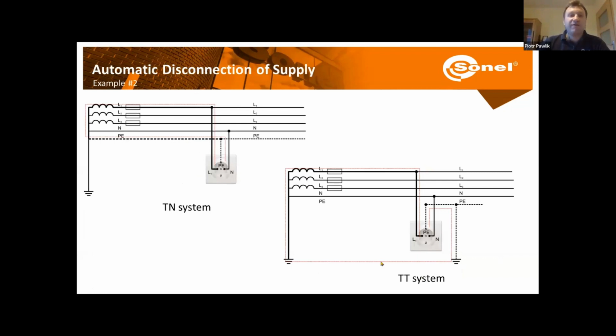Okay, so here lower value will be in case of a TN system. Let's look over here. This is our fault loop, the red dashed line. In case of a TN system, it is closing through a protective wire, so just a piece of metal in insulation. In case of a TT system, the earthing is provided locally, so our loop will close through the ground, the actual earth. Well, obviously a piece of metal, like in case of a PE wire, has a lower resistance than the actual earth or dirt, so that's why lower values will be in case of a TN network.